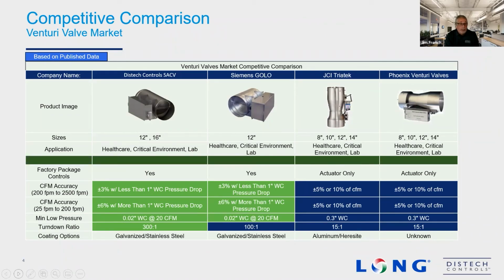As opposed to traditional systems, they measure the velocity and the static pressure at the same point of measurement in a flow ring. In this case, with this technology, we use the single blade damper in the product itself as the orifice plate, and we pick up our static pickup actually behind the damper shaft itself. Using that technology, we're actually able to achieve 100 times magnification of the flow signal and give us that turndown capability to be able to read and measure, accurately control to low flows at a very low velocity.